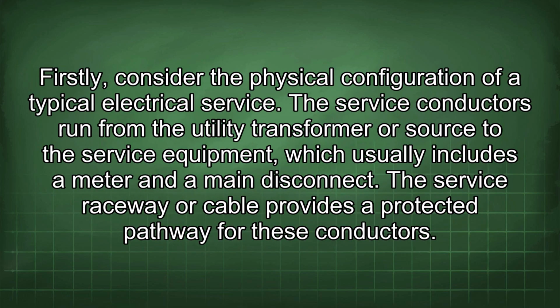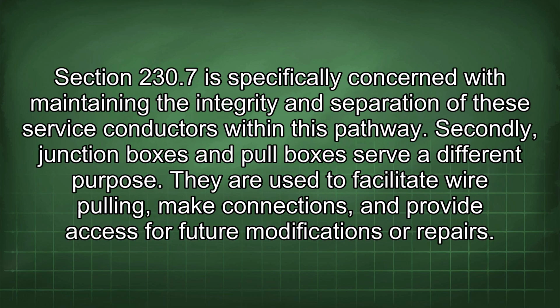Firstly, consider the physical configuration of a typical electrical service. The service conductors run from the utility transformer or source to the service equipment, which usually includes a meter and a main disconnect. The service raceway or cable provides a protected pathway for these conductors. Section 230.7 is specifically concerned with maintaining the integrity and separation of these service conductors within this pathway.